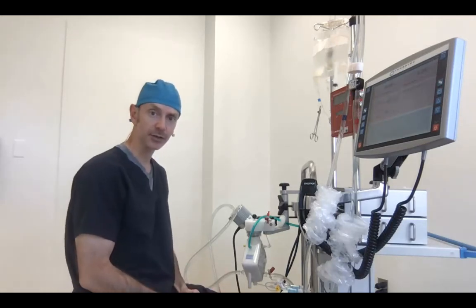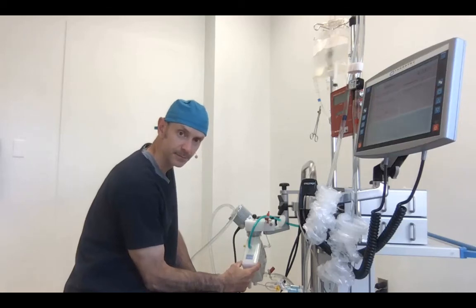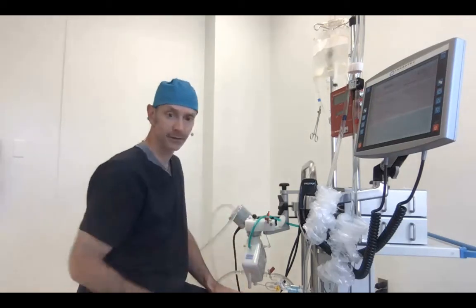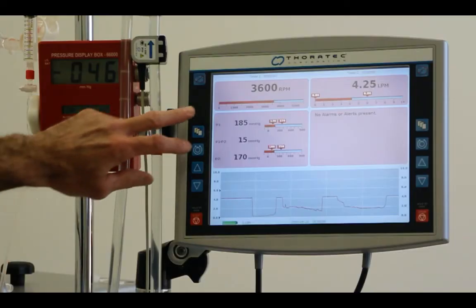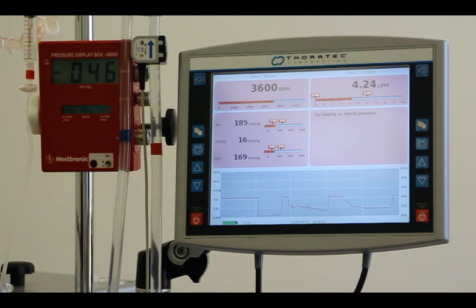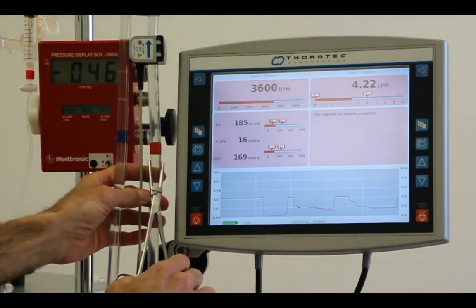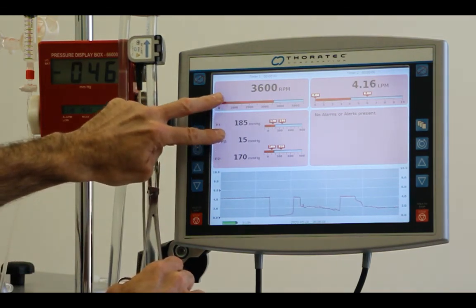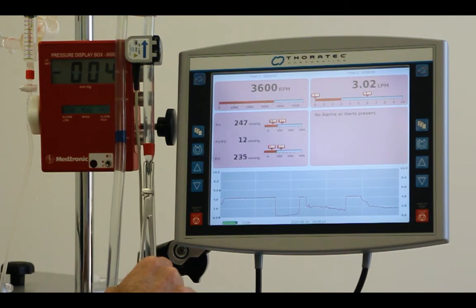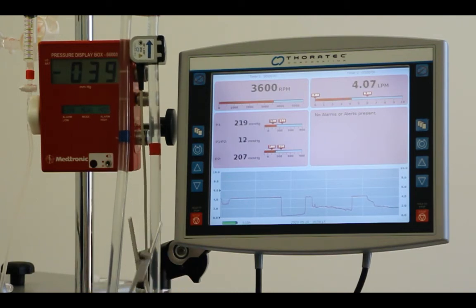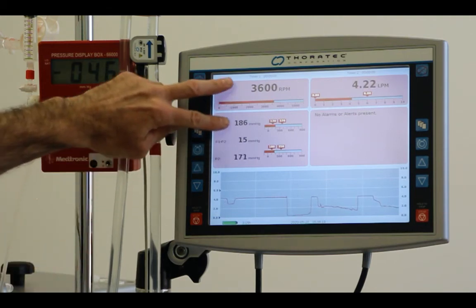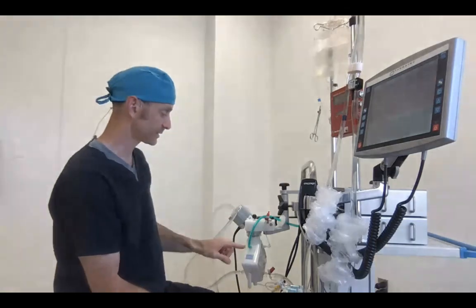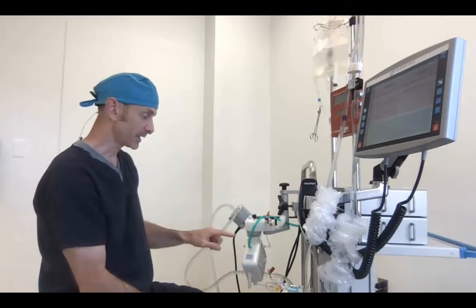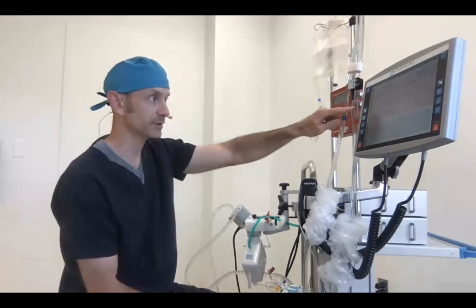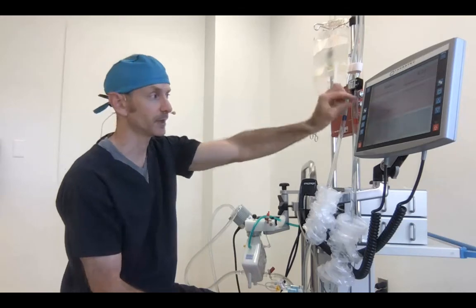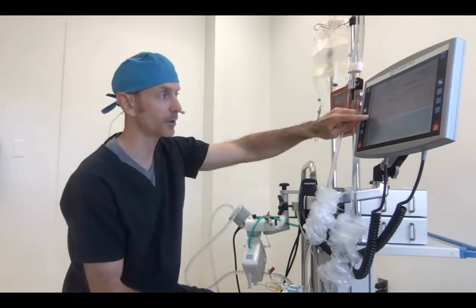Okay, so there's one last section that we have to talk about, and that's this area right here, the oxygenator itself. Now you'll notice if we take a clamp here and watch your P1 and P2, the pre-membrane and the post-membrane, as we add resistance to the arterial, then these numbers go up, and they go up together. They both went up. And if I remove the resistance, then they both come down.